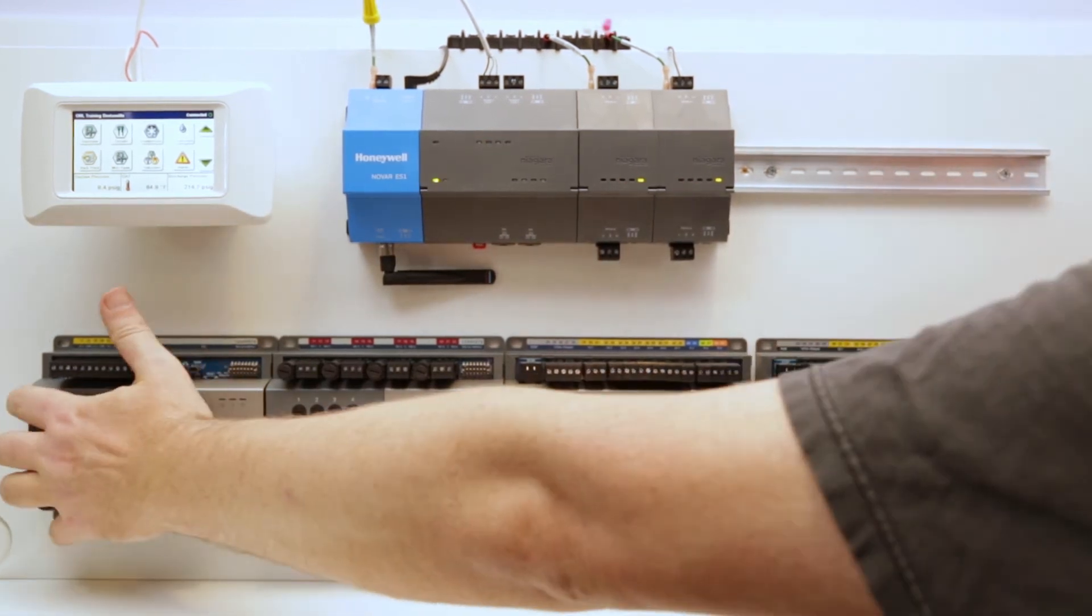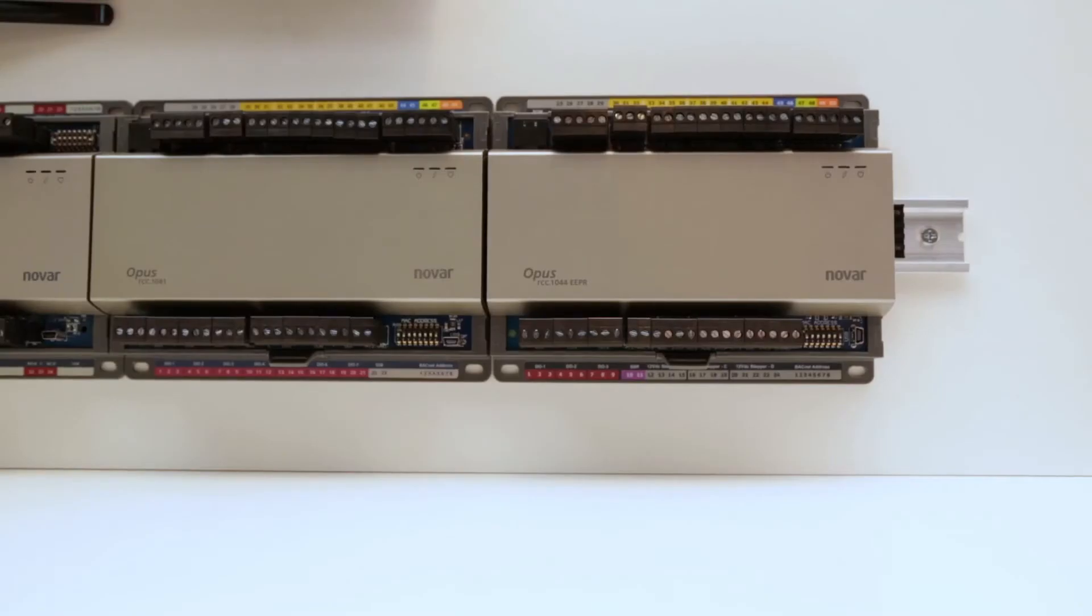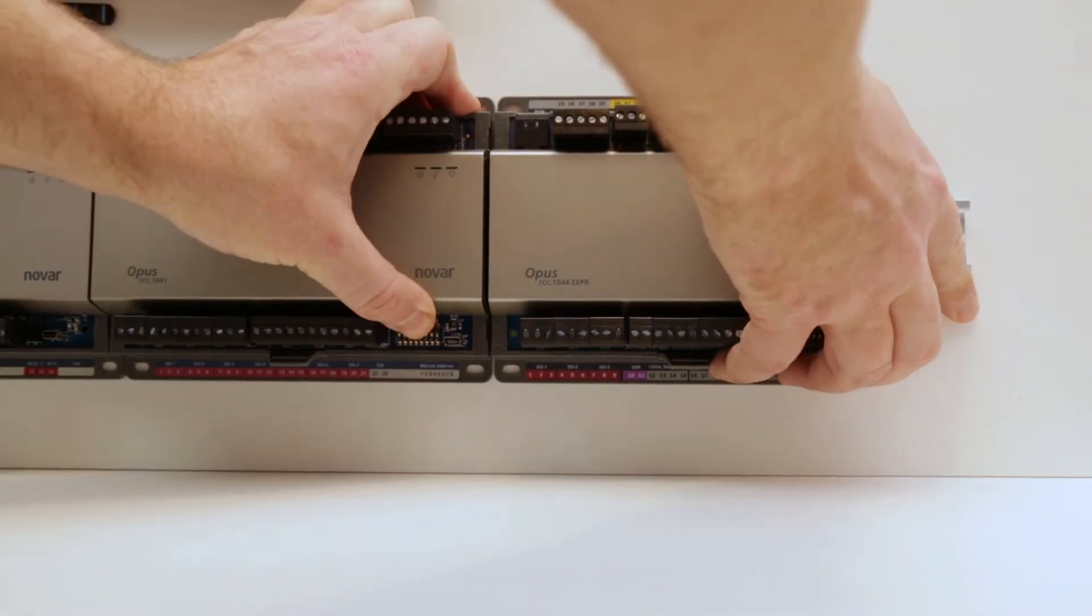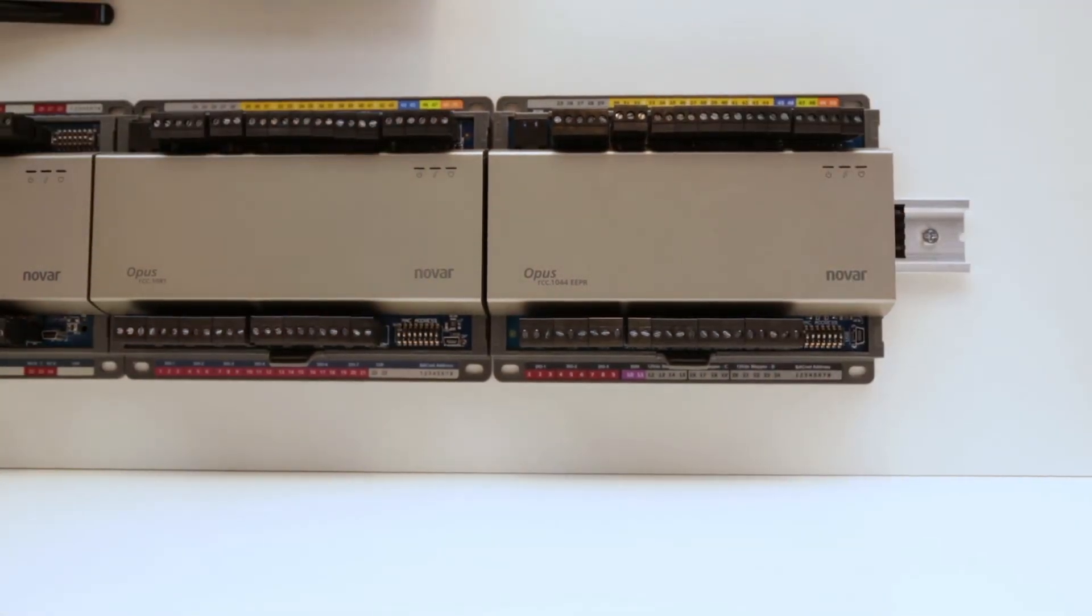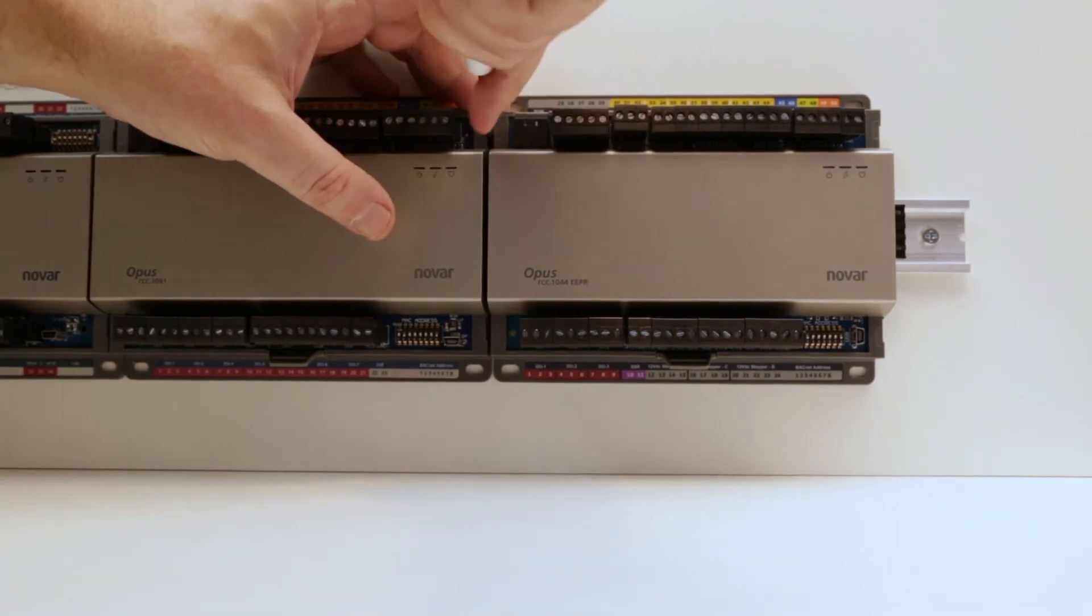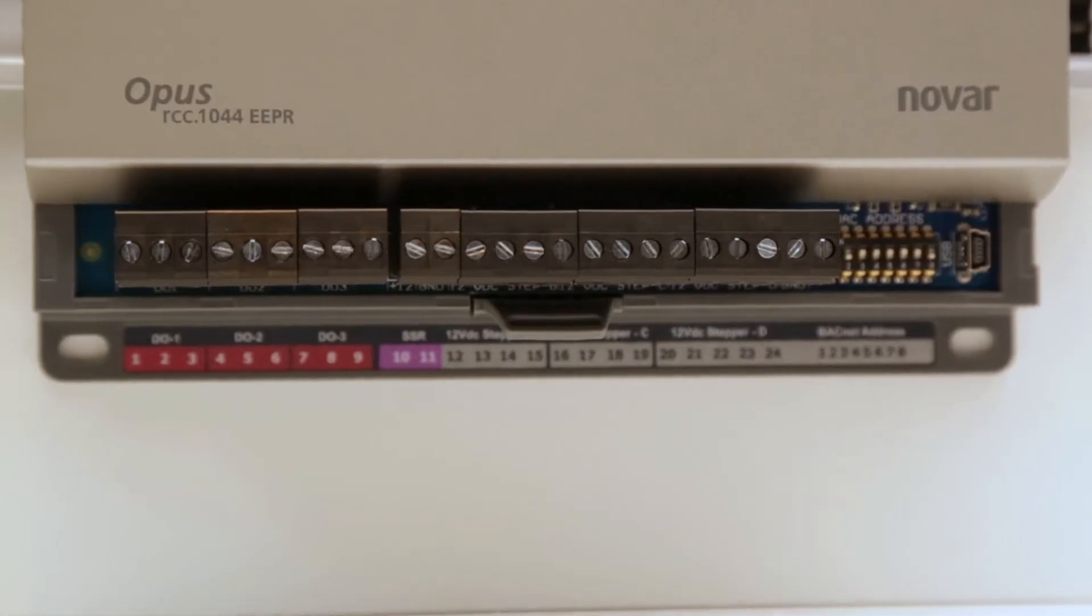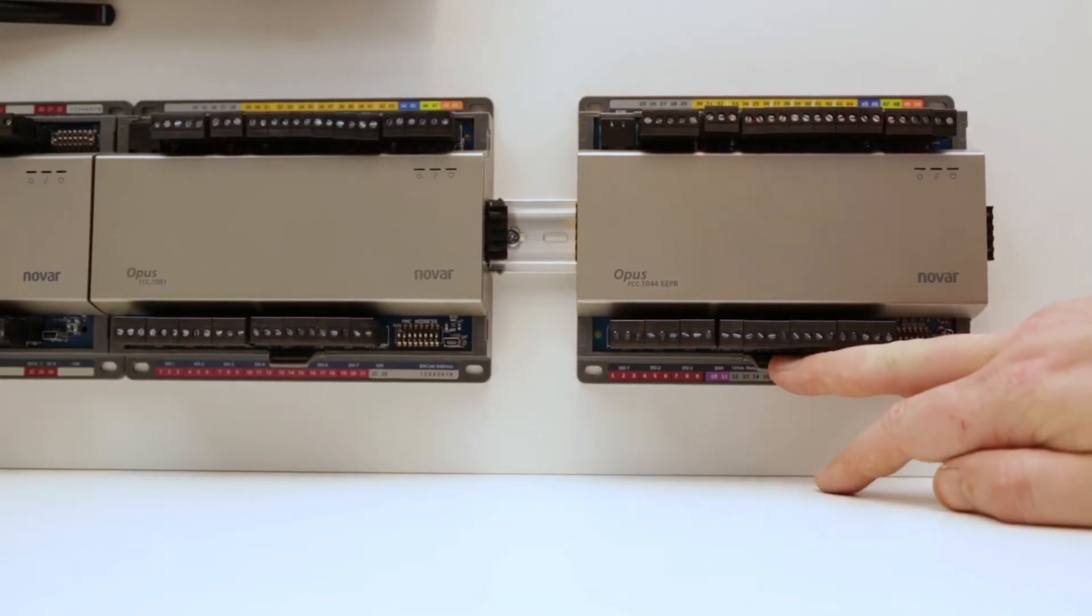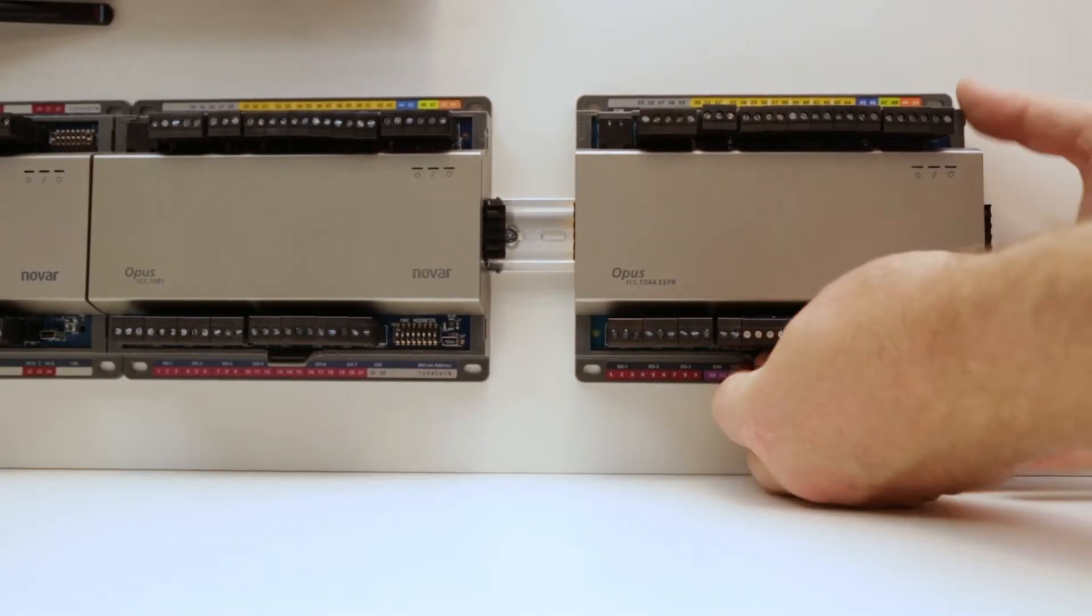To remove a module, simply pull the device being removed from the others in the series. This can be difficult to do on some installations, and a flathead screwdriver may be used to gently pry the bases of the two modules apart. Once separated, pull down on the locking release tab and lift the bottom portion away from the DIN rail.